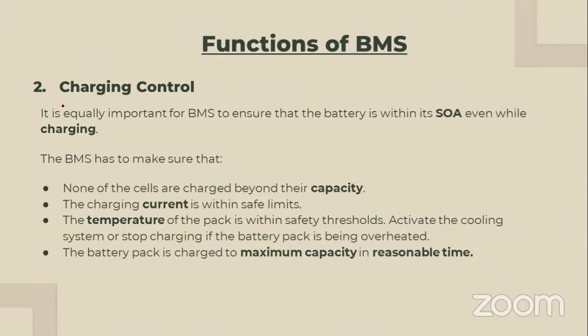So if things are going very bad, and if there is a condition where the temperature of the battery pack is increasing, or the voltage level of certain modules is increasing beyond the threshold or some safety limit, then of course the BMS has to cut down the battery pack from the system. That means it will isolate it, opening the positive and negative contacts to isolate from the system.